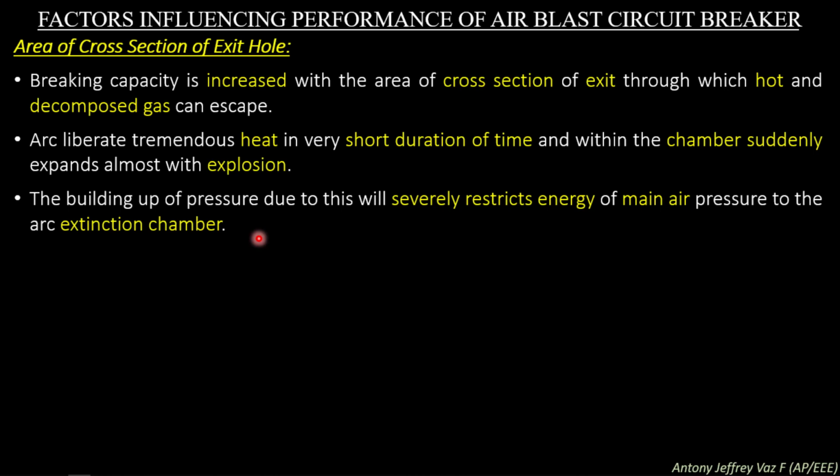extinction chamber will decrease the pressure present in the reservoir. So the air will not flow from reservoir to the arcing chamber. To avoid this effect, the exit hole is present. Once the arc liberates the heat into the air, this explosion effect will exit the circuit breaker through the exit hole.